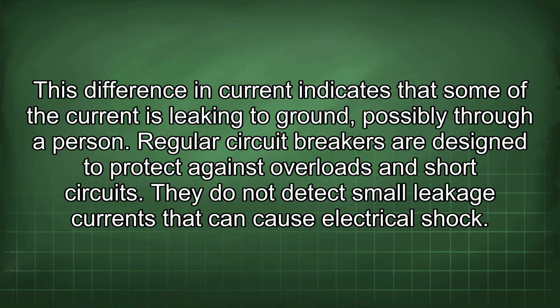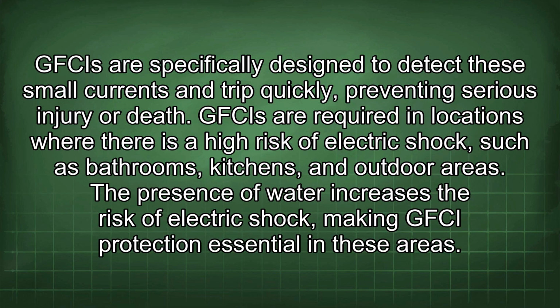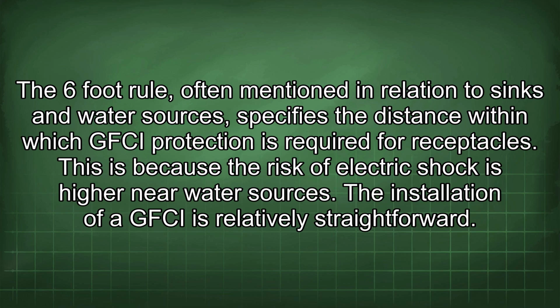Regular circuit breakers are designed to protect against overload and short circuits. They do not detect small leakage currents that can cause electrical shock. GFCIs are specifically designed to detect these small currents and trip quickly, preventing serious injury or death. GFCIs are required in locations where there is a high risk of electric shock, such as bathrooms, kitchens, and outdoor areas. The presence of water increases the risk of electric shock, making GFCI protection essential in these areas. The 6-foot rule, often mentioned in relation to sinks and water sources, specifies the distance within which GFCI protection is required for receptacles. This is because the risk of electric shock is high near water sources.